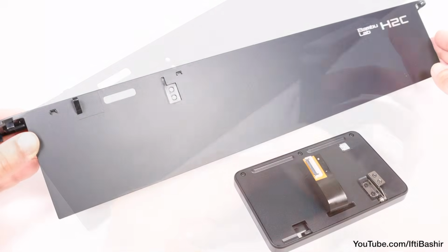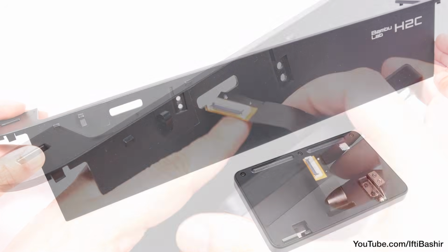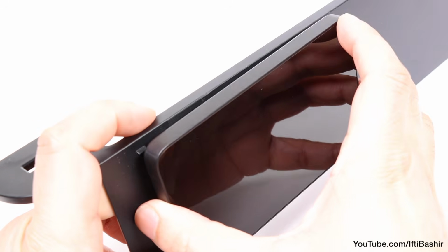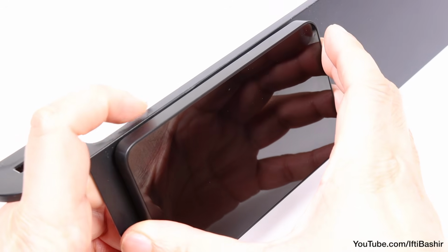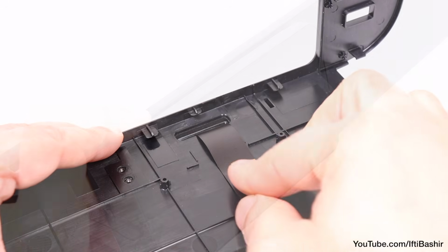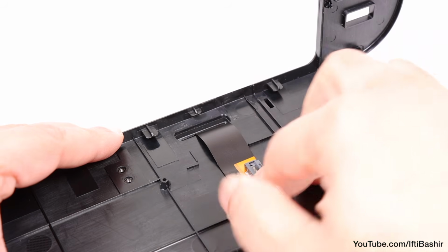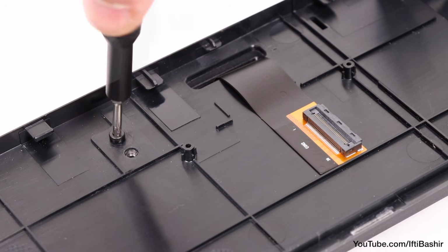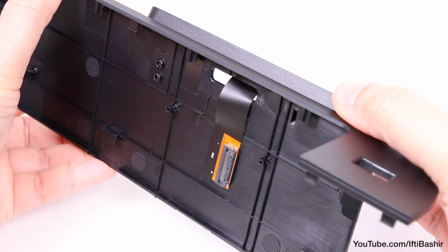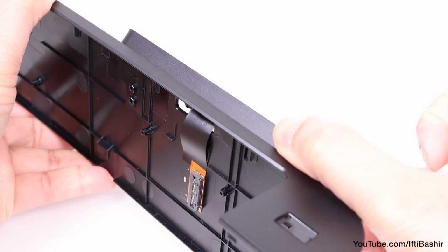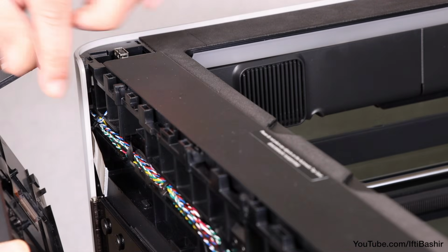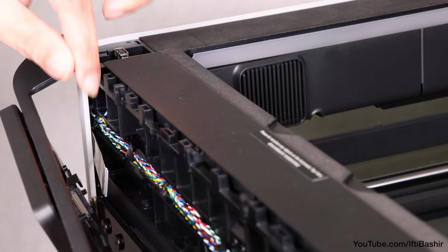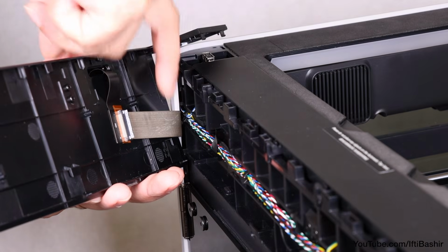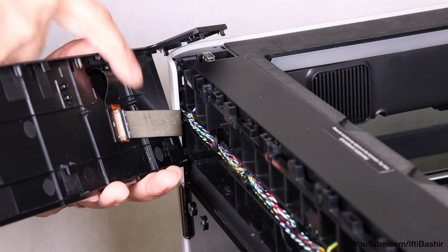Reverse the process to install on the new H2C panel, so pass the connector through the corresponding hole, sliding the display to the left to lock into place, before securing the connector back down, and securing the 2 screws previously removed, now fixing the display screen into position. Bring the panel close to the printer frame and connect the display ribbon cable to the connector, closing the latch to secure it into place.